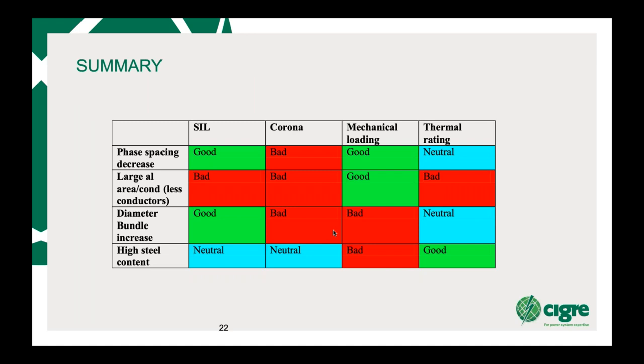So in summary, if we're looking here at what actually affects the AC line, we've got surge impedance loading, corona, mechanical loading, and thermal. So if we decrease the phase spacing, as we said, we reduce the inductance and improve the capacitance. So that for SIL is good. For corona, it's bad. For mechanical loading, it's good because you don't get the moment on the tower if one of the conductors break. Thermal rating, it doesn't really matter.